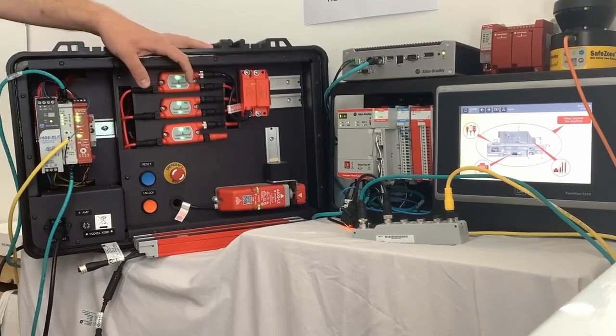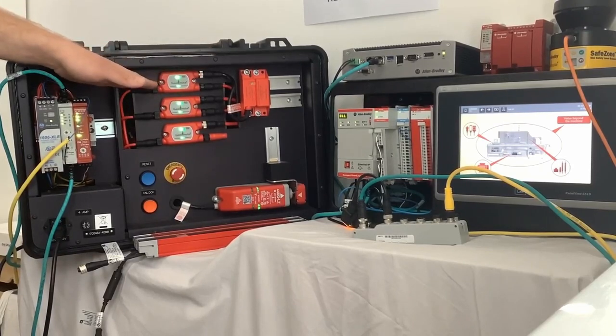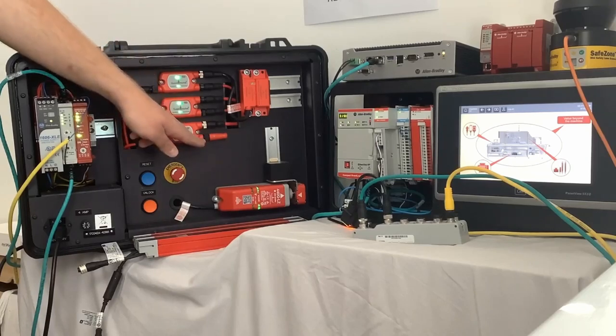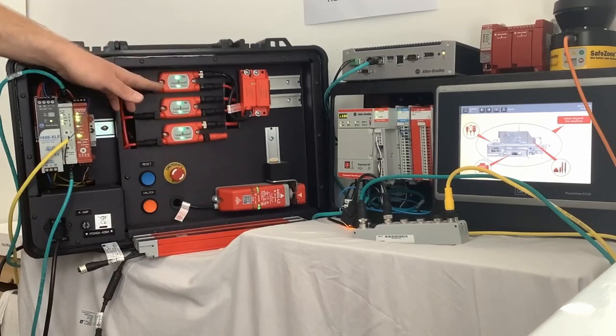The good thing about GuardLink is these nodes do not need to be programmed. You basically put them in from one to 32. When the relay powers up, there's a terminator on the last tap. The first tap it sees is one and it goes up to 32.